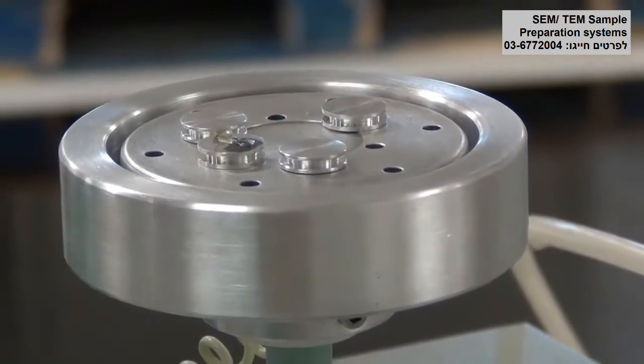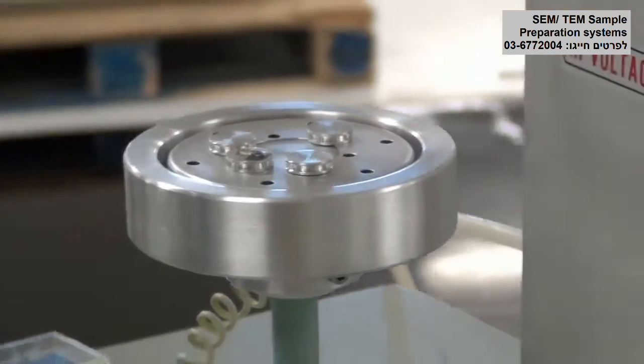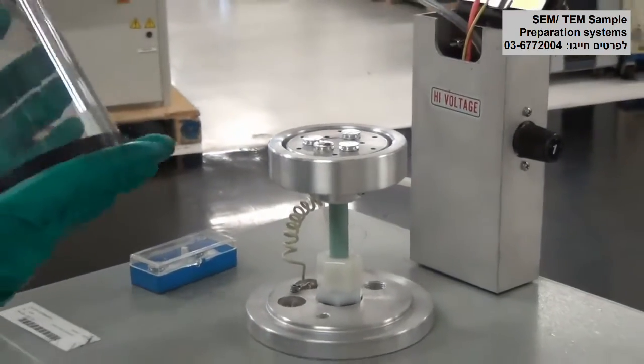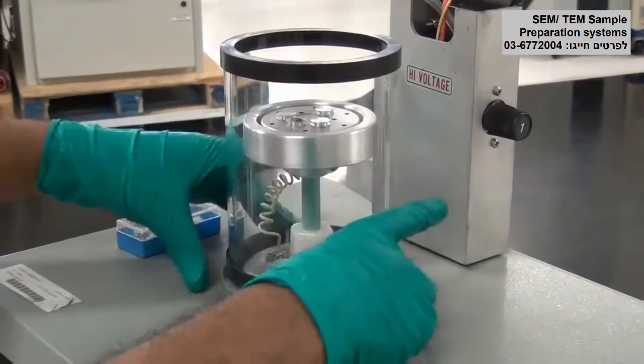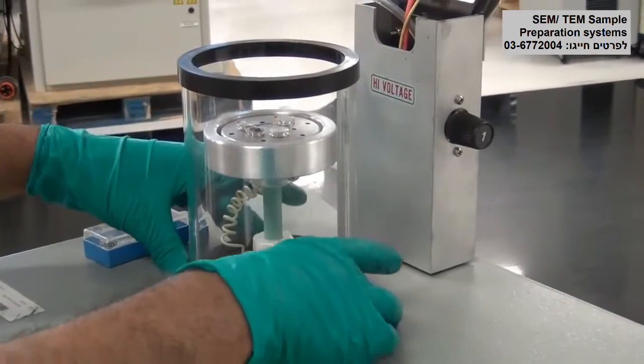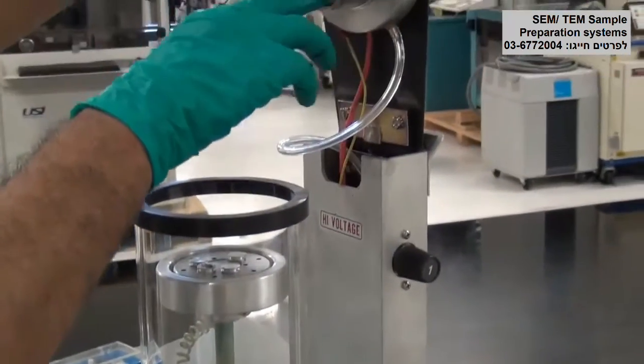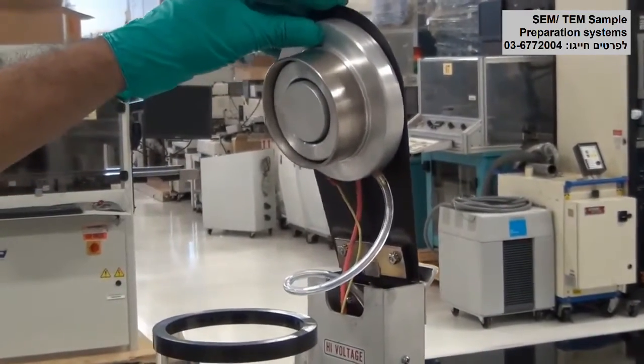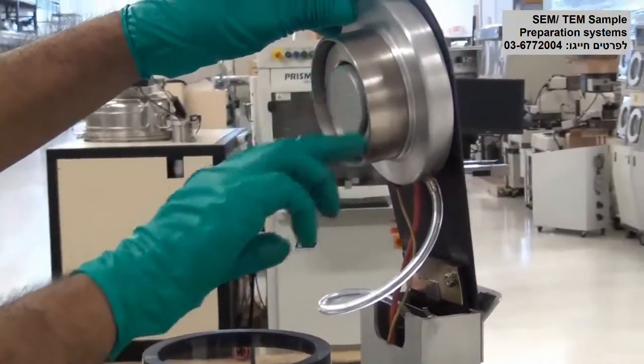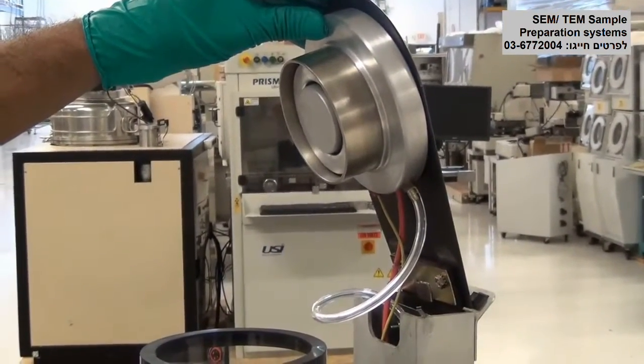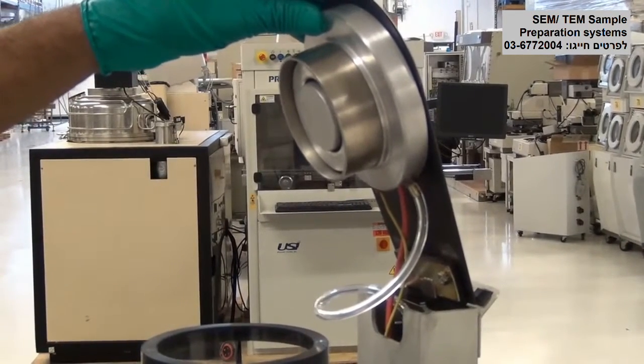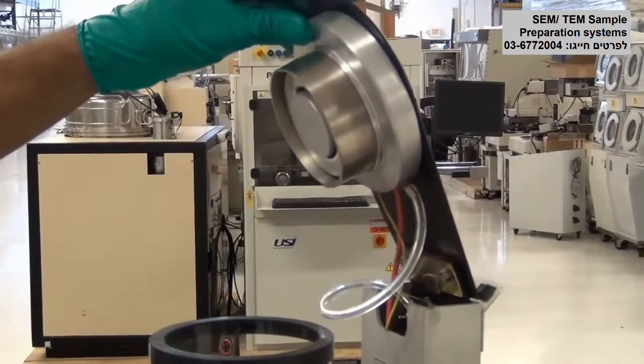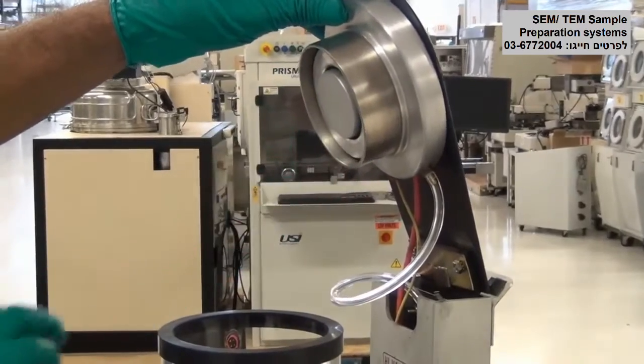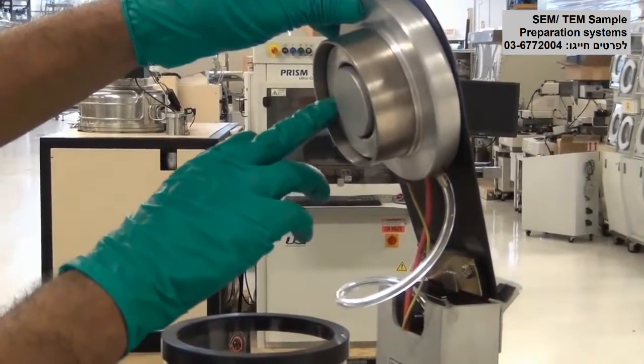And once the samples are installed, make sure that the bell jar is pre-installed with the gaskets. Place the bell jar approximately concentric to the base plate, and I have an aluminum ring here installed which will assist in etch mode. At this moment I don't have a target, but usually an annular ring with the material pre-deposited or available from any scanning electron microscope accessory suppliers. There are different dimensions available. We have to find the right one with the right dimensions. The ID, the inner diameter and outer diameter, should match this ring.